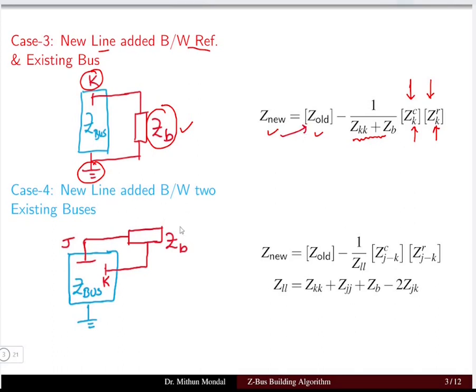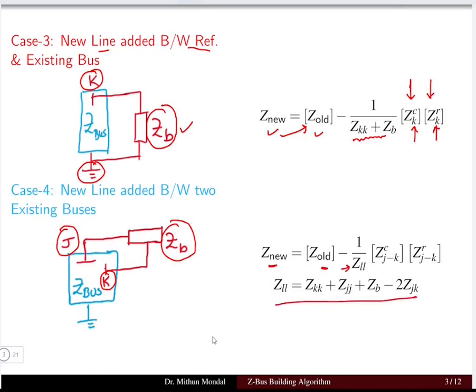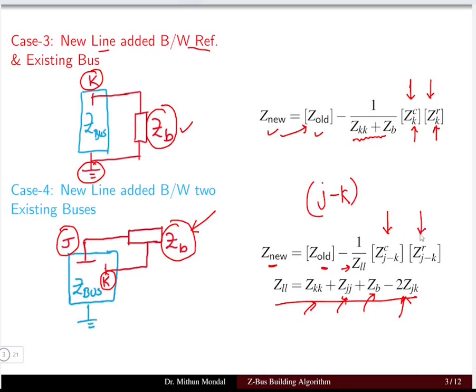Case 4: if a new line Zb is added between two existing buses j and k. The new impedance matrix equals Z_old minus one over Zll, where Zll = Zkk + Zjj + Zb - 2*Zjk, multiplied by the product of (column j minus column k) and (row j minus row k) of the old Z matrix.